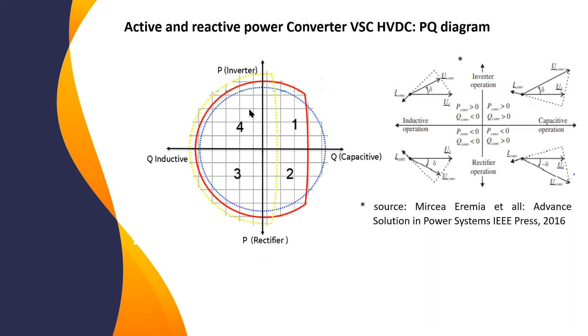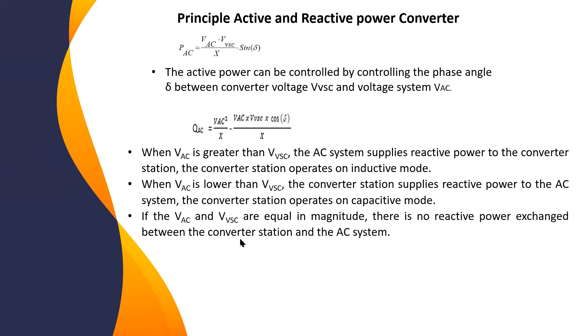This is the scheme here. And then this is the formula when we transfer the power. The active power can be controlled by the phase angle here. And then for AC reactive power, the definition: if the AC system voltage is greater than the voltage created by the valve, the reactive power will be supplied to the converter. The same here, when the VSC voltage is higher than the AC system voltage, the converter can transfer reactive power to the AC system. When we have balance between AC voltage and converter voltage, there is no power exchange.